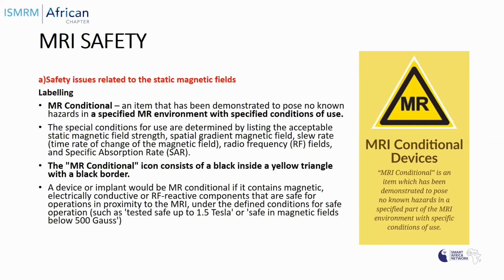If you see this label on devices, then you know that this device is safe with MR. Then we have MR conditional. It's an item that has been demonstrated to pose no known hazards in a specified MR environment with specified conditions of use. The special conditions for use are determined by listing the acceptable static magnetic field strength, spatial gradient magnetic field, slew rate, time rate of change of the magnetic field, radio frequency fields, and then the specific absorption rate. So the MR conditional icon consists of a black inside a yellow triangle with a black border. So MR is written in a yellow background with a black border. These are MR conditional devices.